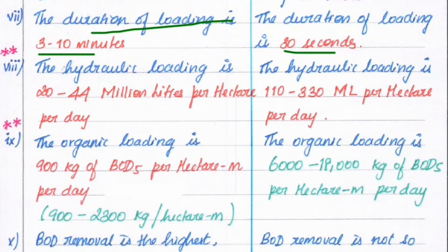The hydraulic loading in the slow rate trickling filter is 20 to 44 million liters per hectare per day, but the hydraulic loading in the fast rate trickling filter is 110 to 330 million liters per hectare per day.